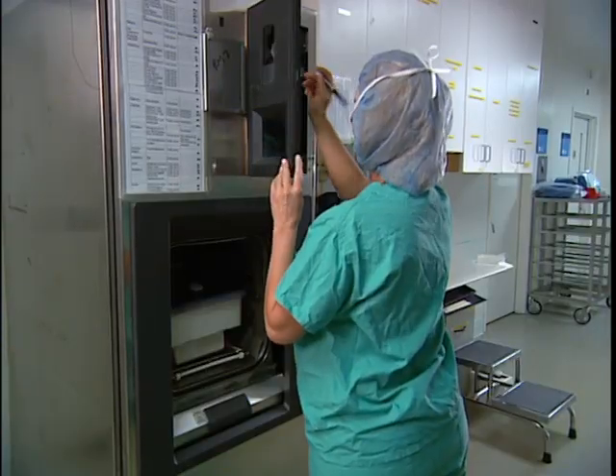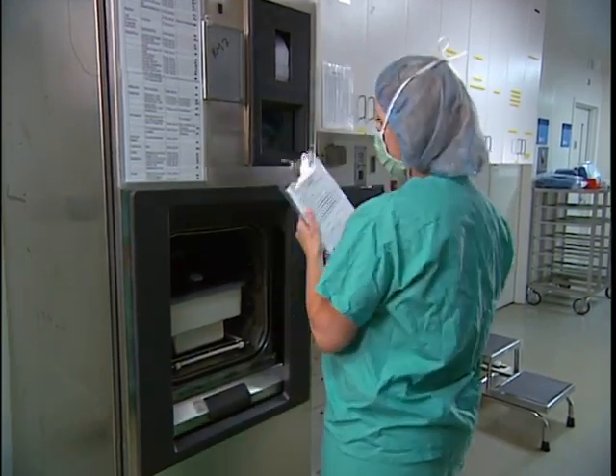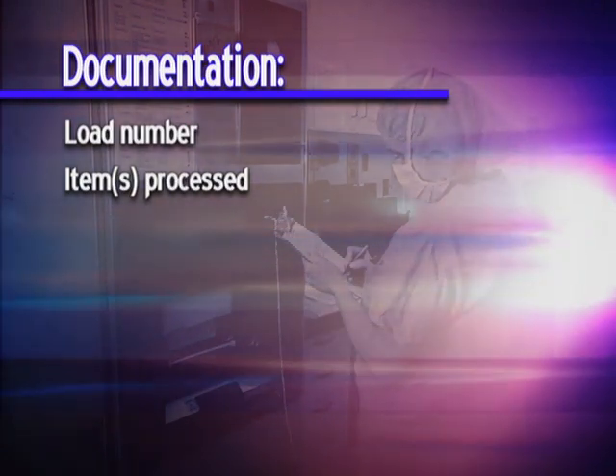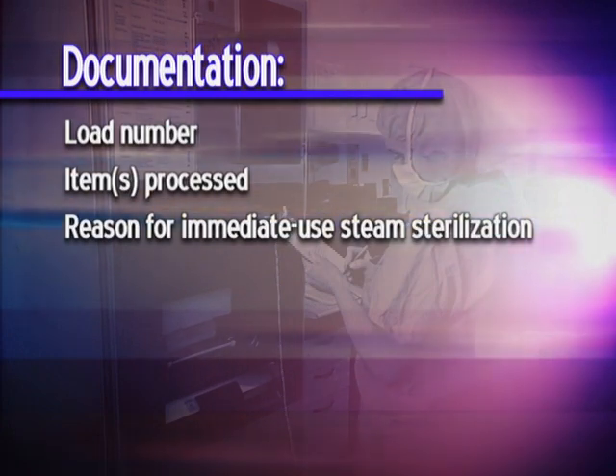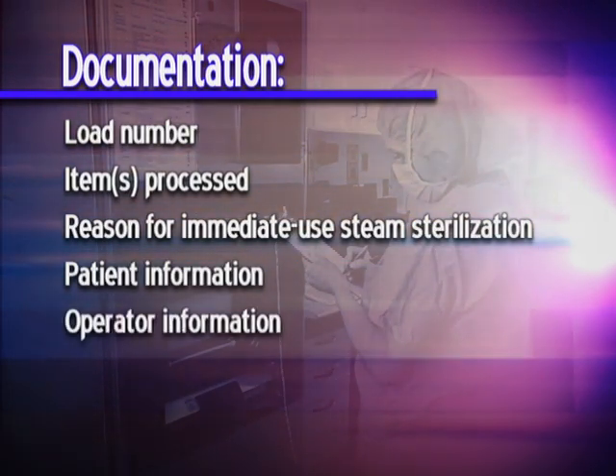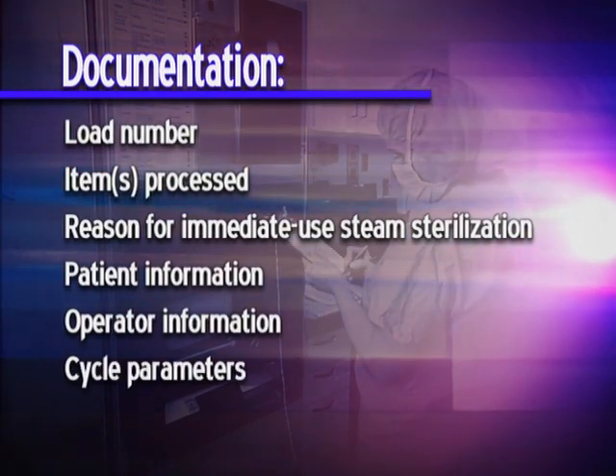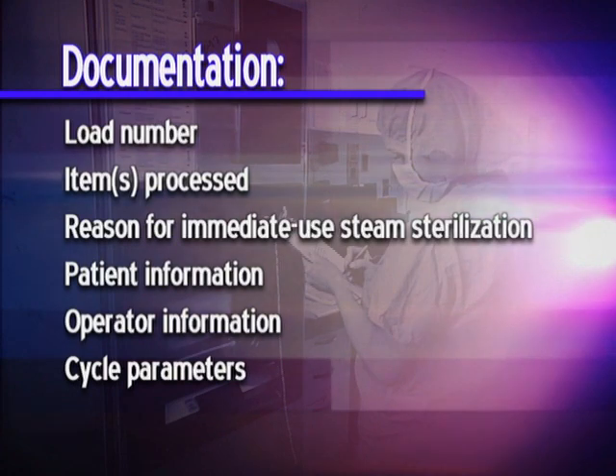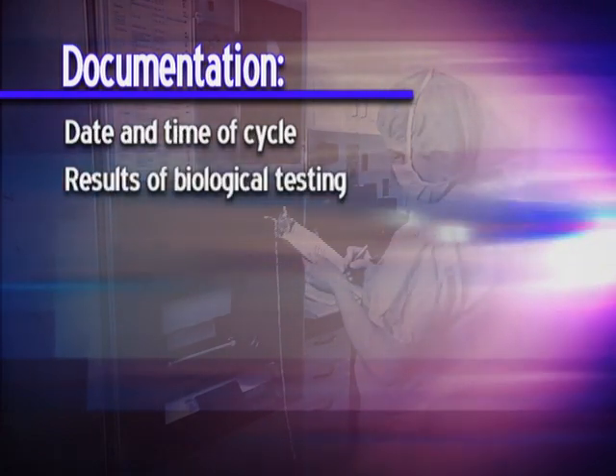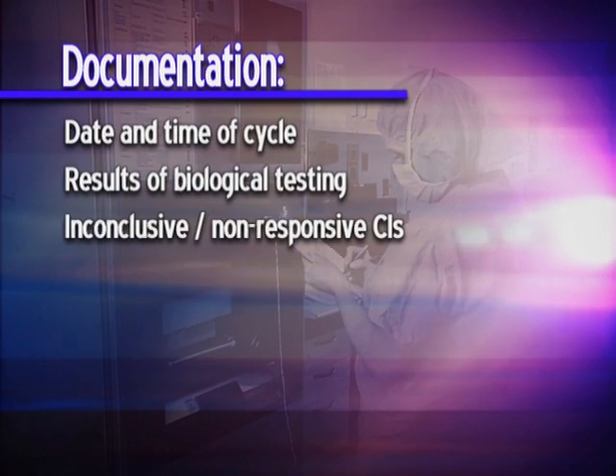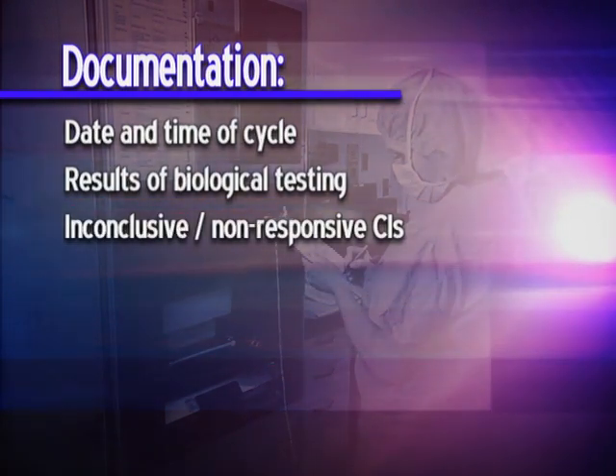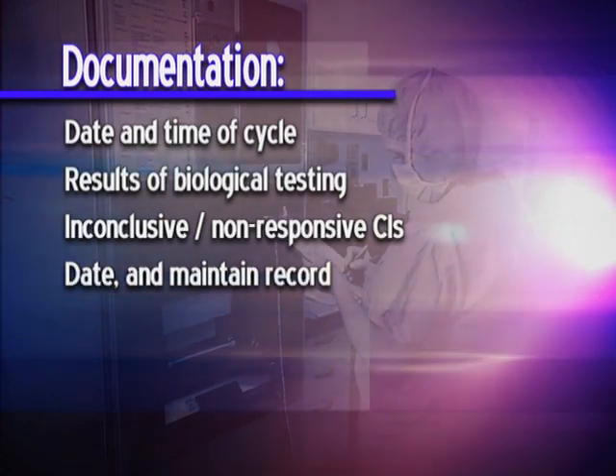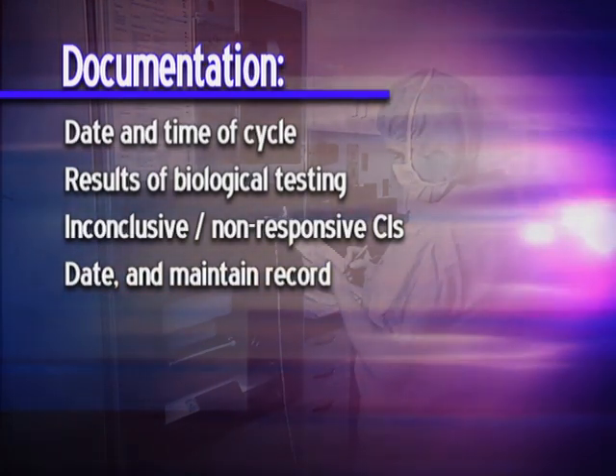Sterilization records should maintain accurate, detailed information on each load, including the load number, the contents of the lot or load, including quantity and a specific description of the item, such as type of instrument, the reason for immediate use steam sterilization, the patient receiving the item, the name or initials of the operator, the cycle parameters, such as exposure time and temperature, if not provided on the sterilizer printout, the date and time the cycle was run, the results of biological testing, if applicable, and any reports of inconclusive or non-responsive CIs found in the load. The time and temperature recording chart, printer, or tape should also be dated and maintained.